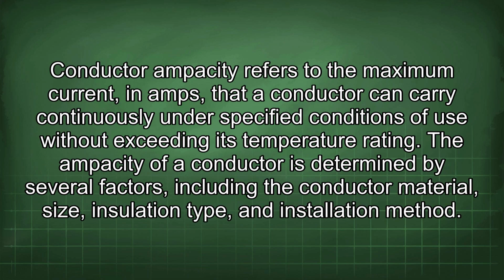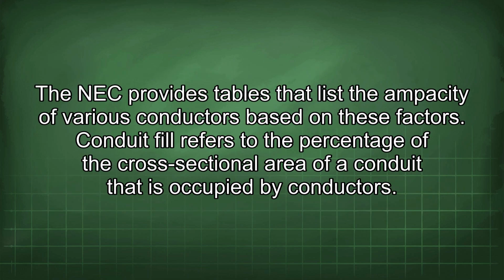Conductor ampacity refers to the maximum current, in amps, that a conductor can carry continuously under specified conditions of use without exceeding its temperature rating. The ampacity of a conductor is determined by several factors, including the conductor material, size, insulation type, and installation method. The NEC provides tables that list the ampacity of various conductors based on these factors.